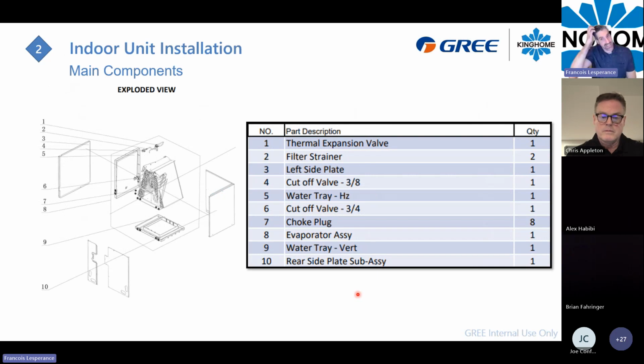So what's inside that A-coil? We're using a thermal expansion valve, so no power needs to be supplied to this kind of A-coil. It's only a thermostatic expansion valve. You will find a strainer at the inlet and the outlet of that valve. Also, you have a cutoff valve, a 3/8 service valve on the liquid line, and on the suction line you will have a 3/4. So for any size of unit, from 2-ton to 5-ton, you will use 3/8 on the liquid and 3/4 on the suction line.